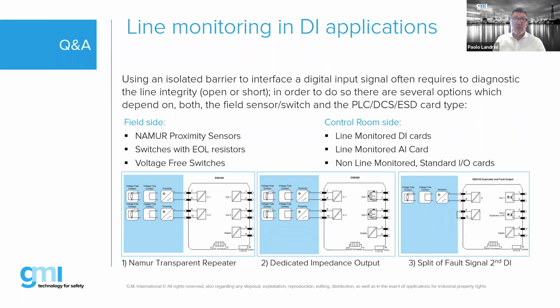To do this, you can use an isolator which repeats a Namur sensor. So take a Namur sensor input and gives a Namur sensor output. However, much depends on the controller card that you are using. If you're using an ESD card that has line monitoring facility, then you can see this information. Some are Namur compatible, some are not Namur compatible. Some have designed their own sets of line monitoring information. That is why we have applications where you can have an isolated barrier that transfers a signal, open, closed, through a set parameter of basically resistance. We fix the resistor value to match those of the DI card. So you have many, many versions to comply to a Yokogawa controller, to comply to an Emerson controller, but basically you can transfer this information transparently.